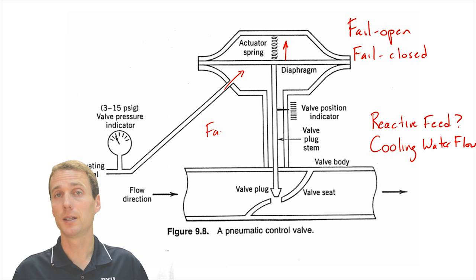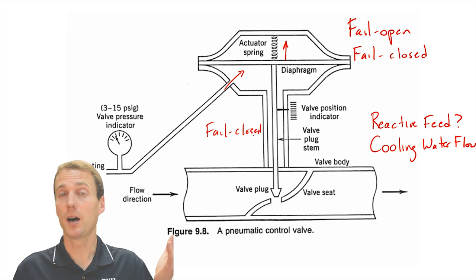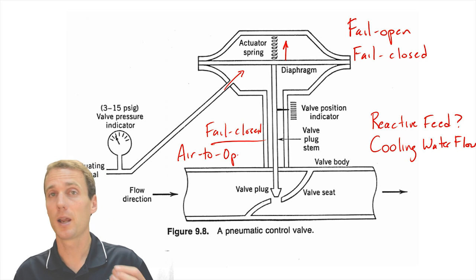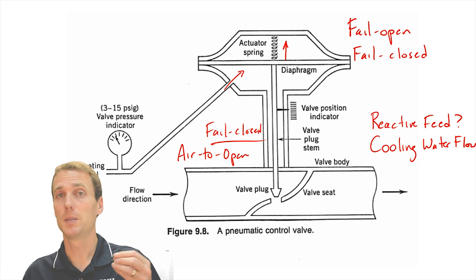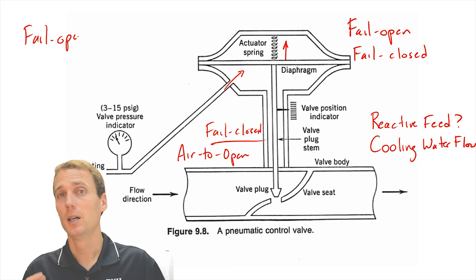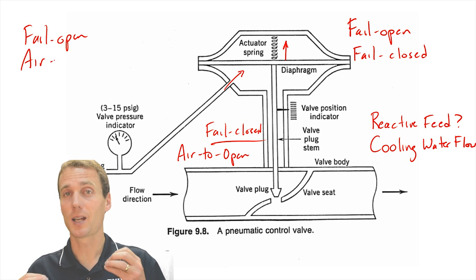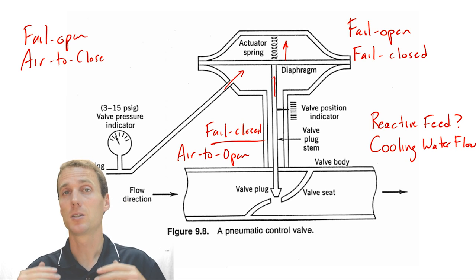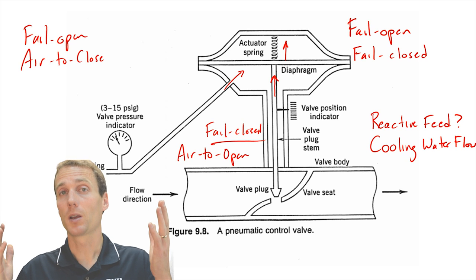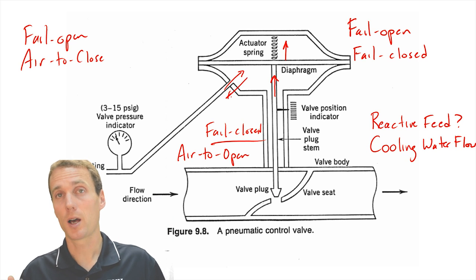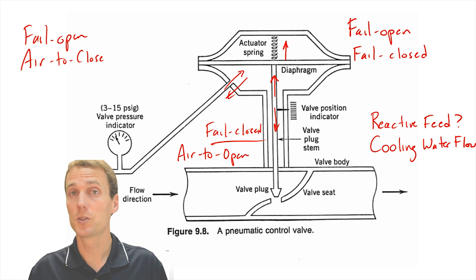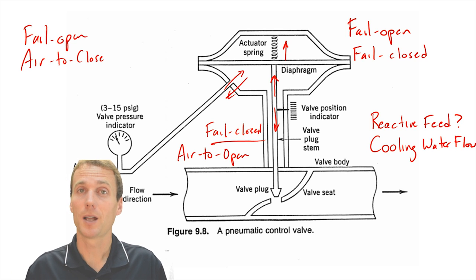If you have a fail-open valve, then it's air to close it. It just depends on where the air is being input into the system. There's often a diaphragm, and as we pressurize one side of that diaphragm, it's going to cause the valve stem to rise. And then as the air pressure is lost, the valve stem is going to close. So this valve, for example, is going to be a fail-closed or air-to-open type valve.